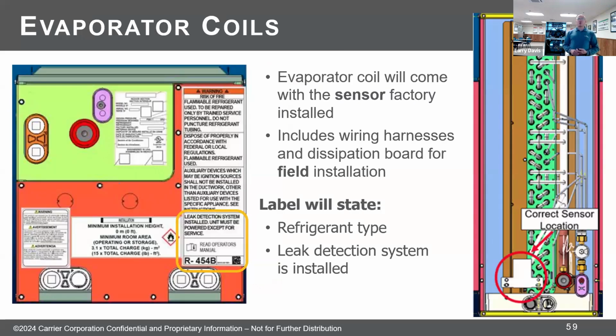On your evaporator coils, once again, just reiterating that it's going to have the labeling on there. Now, you don't want to disrupt or tear up that label. Make sure it's still legible. Try not to smoke it with a torch if you're brazing. And make sure that sensor is in the correct location, especially if you're on a multi-poise coil and you flip it to horizontal.